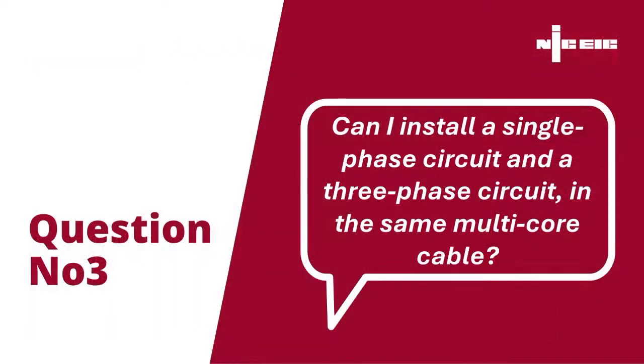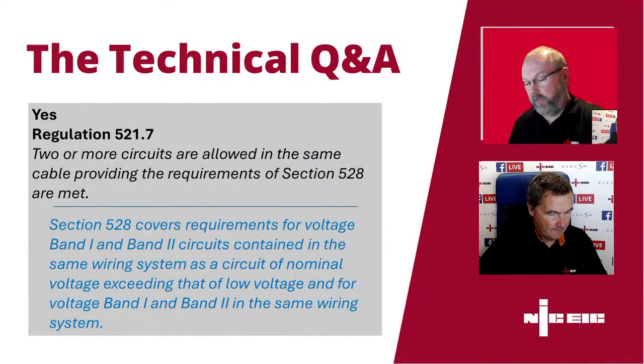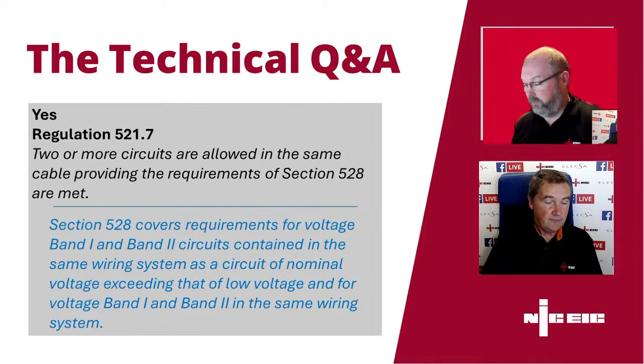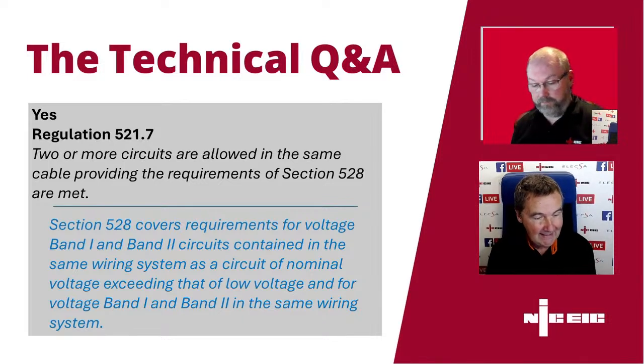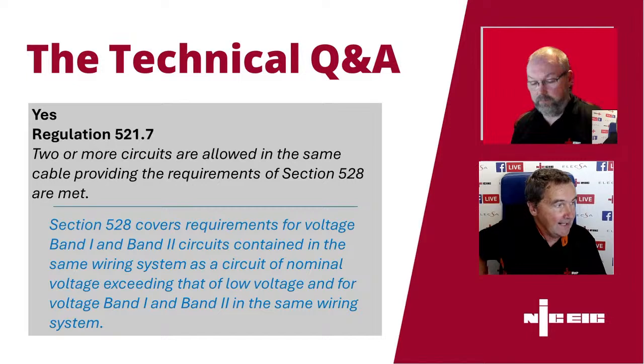Okay. Another question. Can I install a single phase circuit and a three-phase circuit in the same multi-core cable? Again, a common question that we do get asked, again normally in larger installations. What's our thoughts there, Craig? Yes, it is permitted, and on regulation 528.1, it gives examples of what you need to comply with to meet that requirement, and 521.7 refers as well. So 521.7, we've thrown it up on the screen there. That clearly says, so there is a regulation that clearly defines that it can be done.